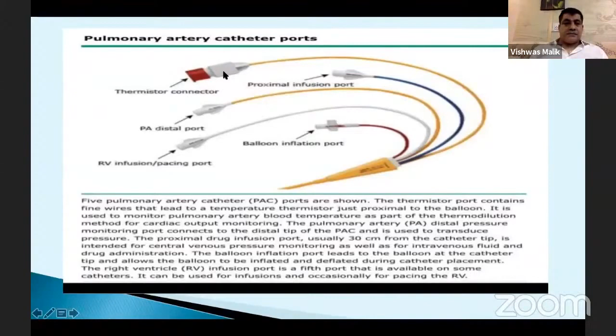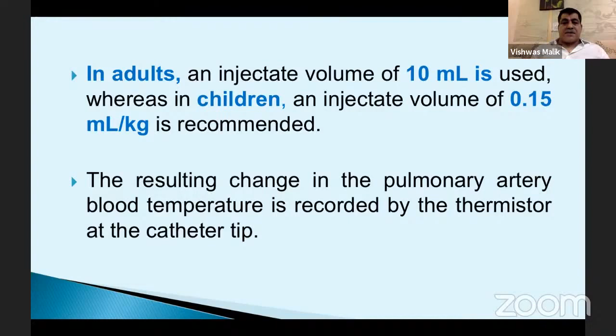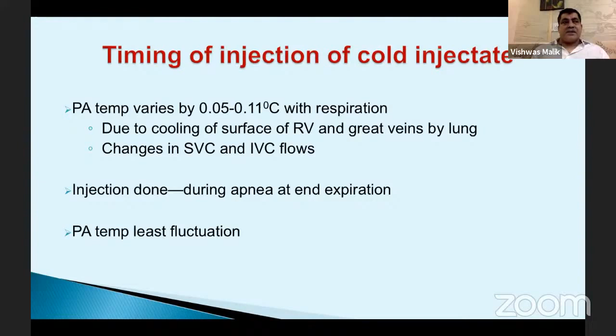In adults, the injected volume is kept around 10 ml, whereas in children, it is kept around 0.15 ml per kg. The resulting change in the pulmonary artery blood temperature is recorded by the thermistor at the catheter tip. The timing of the injection is crucial for measuring accurate cardiac output, and the PA temperature varies in the different phases of respiration. So it needs to be done at the end of expiration, and preferably apnea is instituted if feasible, since there are fewer temperature fluctuations at this time. So the ideal time of injection is at the end of expiration, and preferably a period of apnea of 5 seconds.